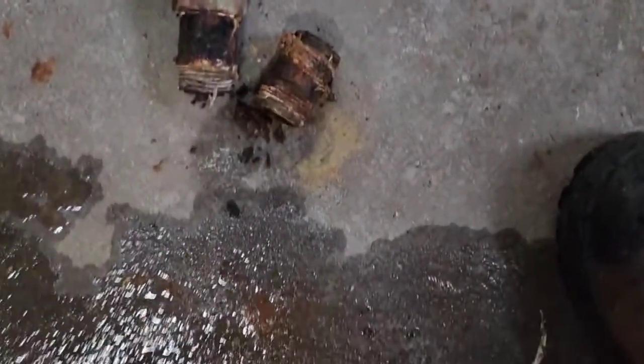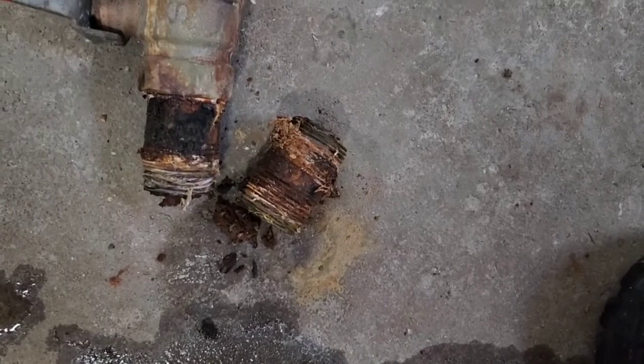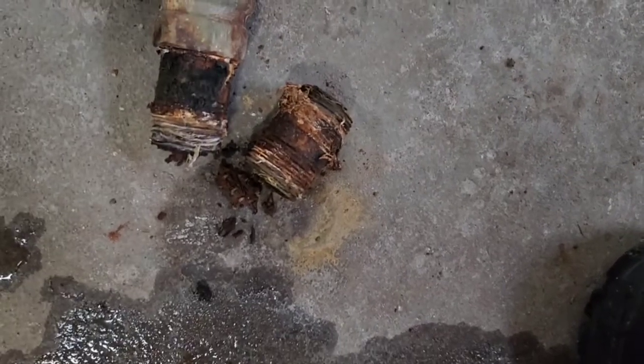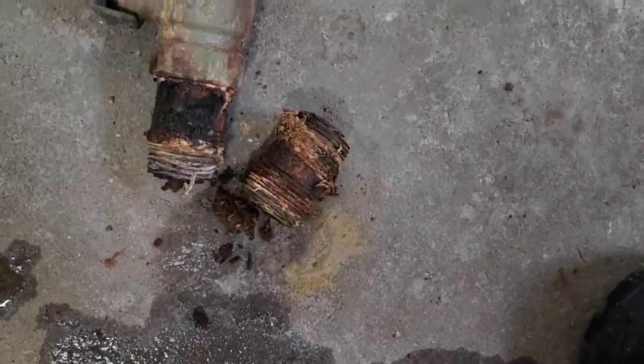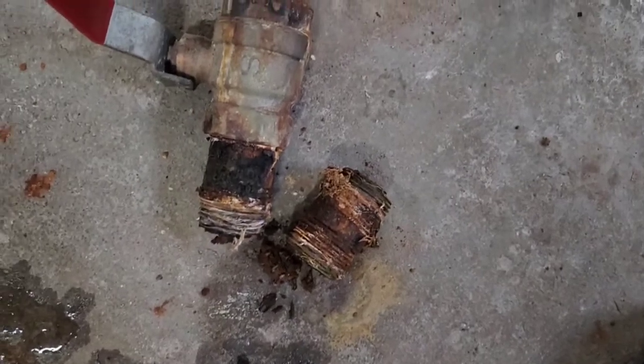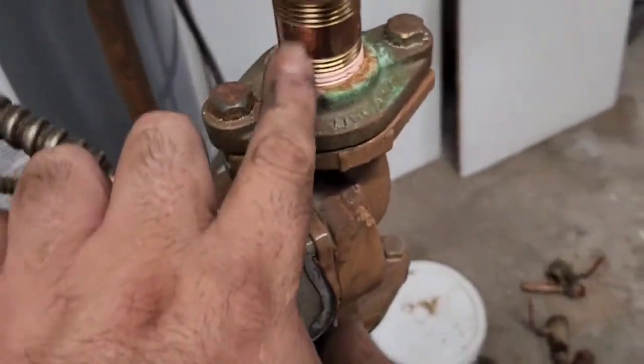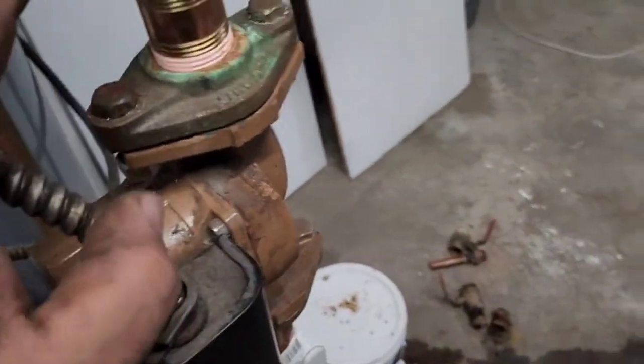These are used for gas piping. You can't use this for domestic hot water, so that's a big no. You need to use brass. Literally, your shut-off valve should be rated.